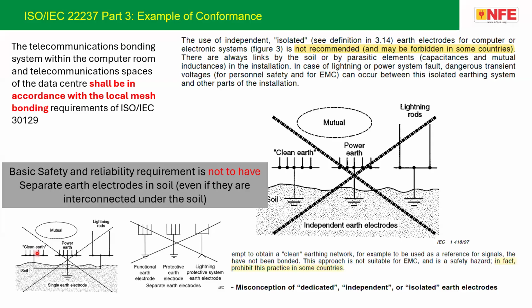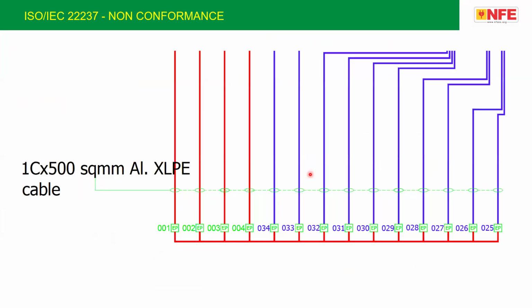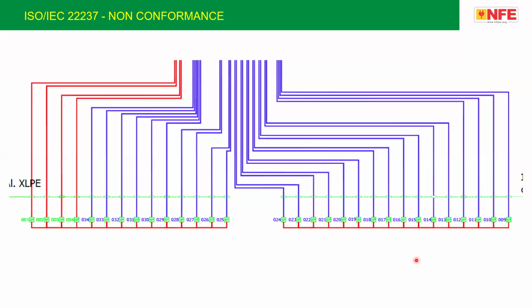Yes. So basically, it is a compliance requirement in the standard not to have a separate earth electrode in soil. If you put separate ones, it's actually a violation of this entire standard, whether it is TIA or ISO/IEC or the upcoming institute or whatever. I'm just showing you one of the pictures which I received recently. This is from a data center. You can see 500 square millimeter XLPE aluminum cable going to earth pit 1, 2, 3, 4 up to 25 on the left side, another 25 on the right side.